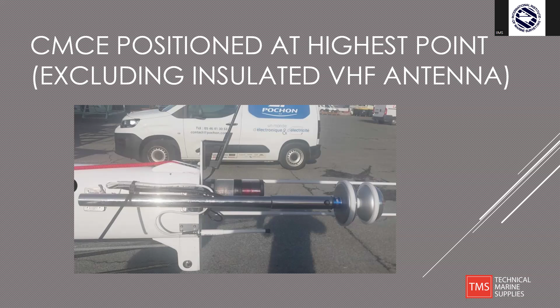Okay, that would be a typical grounding bus, your main channel coming down, your main primary conductor from the device through the mast, wherever it might be, or the arch, down to the little simple bus bar that would then go off to each side of the vessel for the grounding plates.